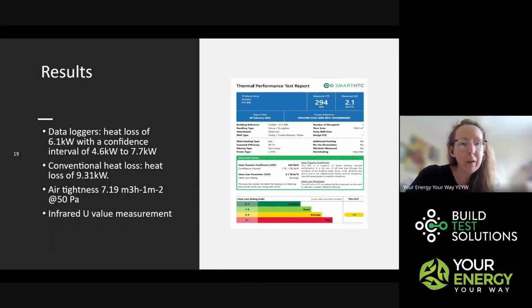It was a little bit too much of a leap for me as an installer to suddenly go in and say, well, let's just put in an 8 kilowatt heat pump. Of course, we'd also done the air tightness test, and that actually came up really pretty low for a house of this age.